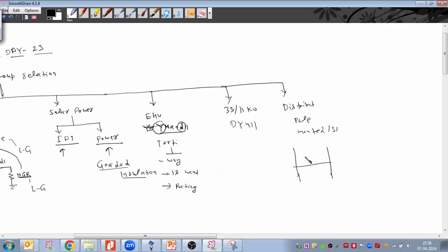On the 4-pole, we are mounting the distribution transformer that could be 100 kVA or 200 kVA, taking 11 kV or 33 kV from the distribution substations, stepping it down to 400 volts, and from this 400 volts again feeding the end load, the consumer. So in that case, what vector group do we use and why do we use that vector group?